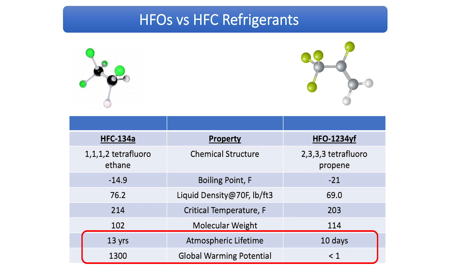The atmospheric lifetime is directly related to the GWP — the global warming potential. So when you end up calculating the global warming potential, you see what a big difference you could get between something like R134A and R1234YF. This is one reason why certain applications such as automotive air conditioning, mobile AC, converted directly from R134A to R1234YF. So just about every new car rolling off the assembly line these days is going to end up with R1234YF as a refrigerant under the hood.